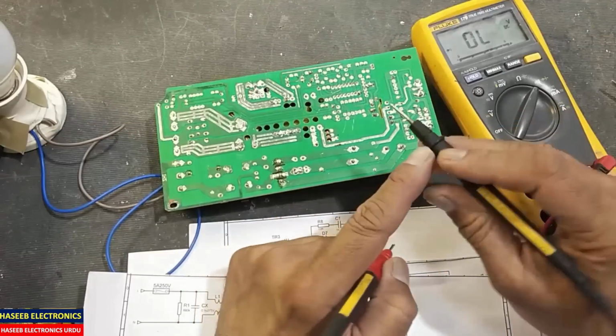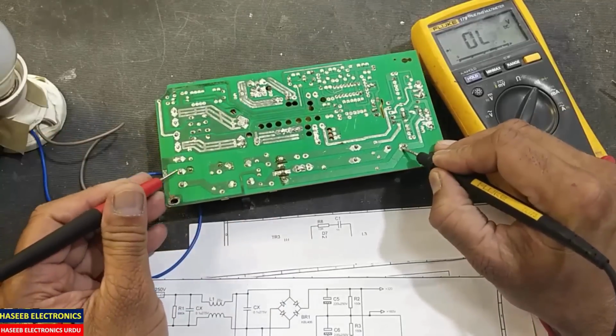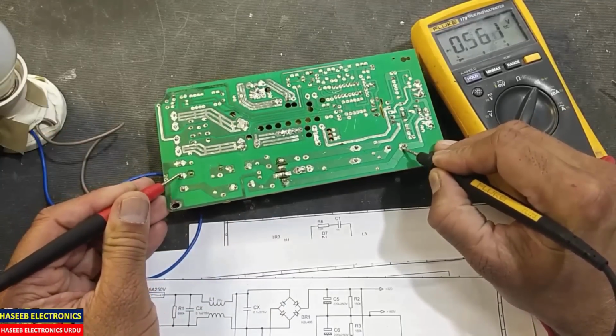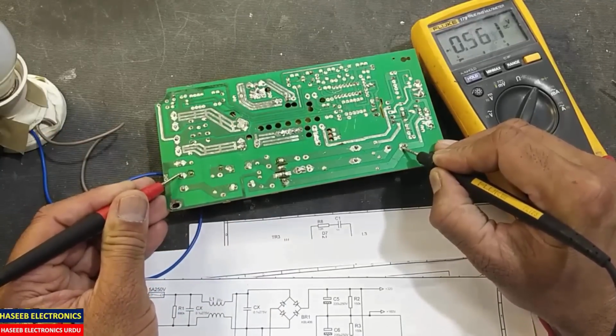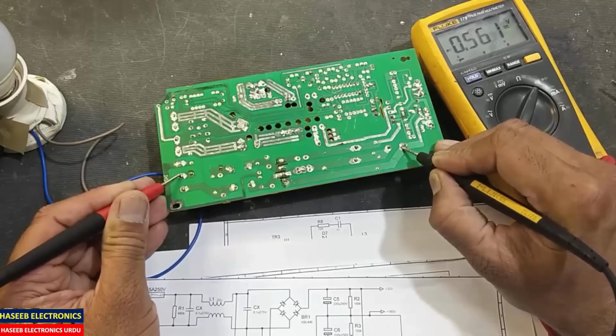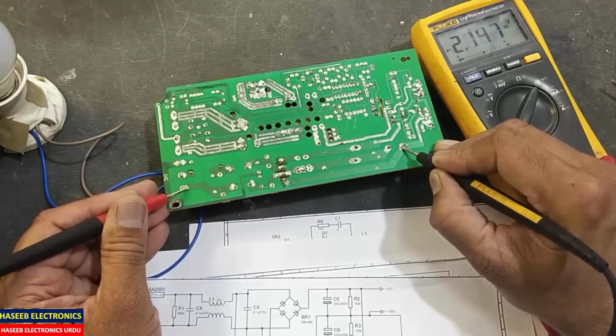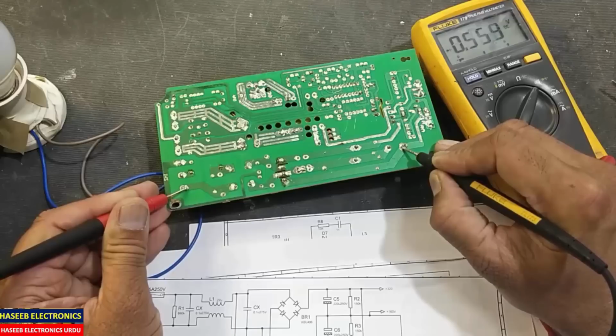Use a lamp or some resistive load to discharge it instead. Set the multimeter to diode mode. Black lead to the positive terminal. Connect to one input terminal, AC input terminal, one diode, 0.561 voltage drop. Second input terminal, 0.561 voltage drop.